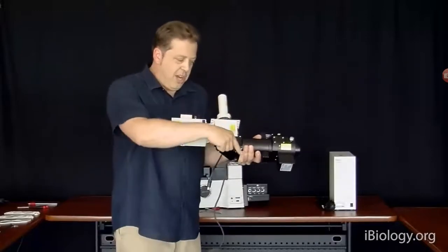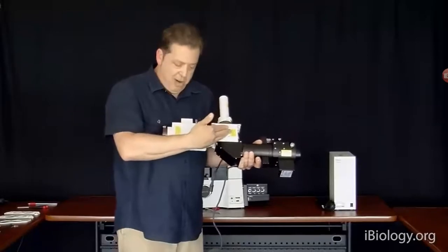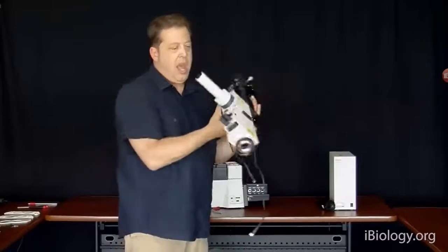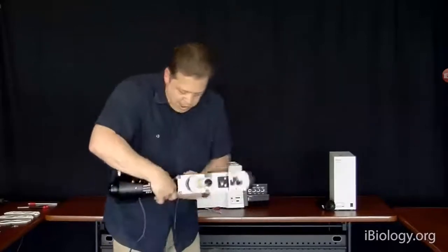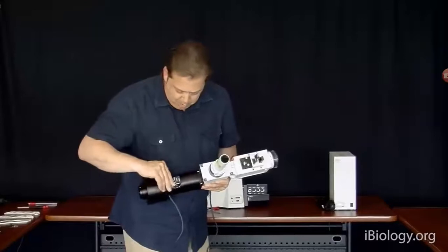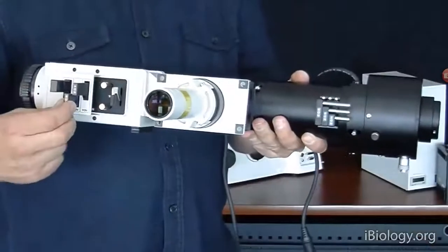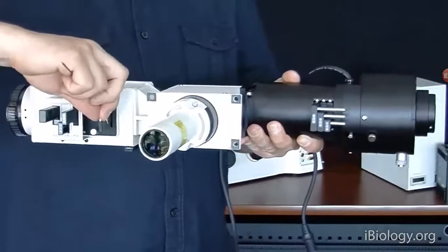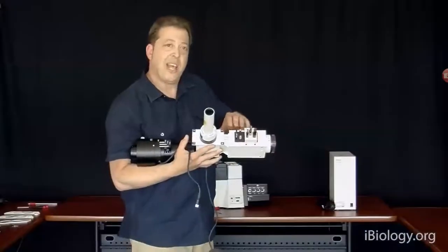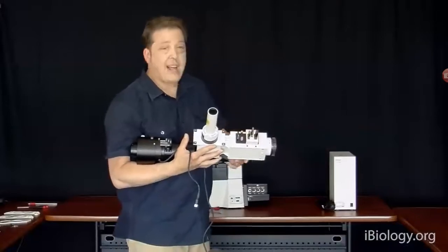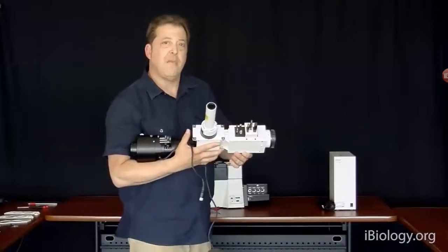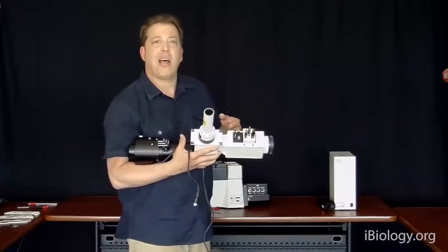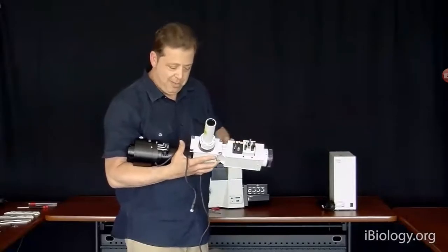There's an optical merge system here. There's a mirror here and then a motorized mirror here, and standard wide field epifluorescence through the other side. And you can see here on both sides, we've got multiple neutral density filters, as well as an aperture diaphragm on the epifluorescence side. The aperture diaphragm in the case of epifluorescence won't actually change the resolution of the system, but will act more like a neutral density filter and attenuate light, allowing you to decrease the amount of light to the specimen.